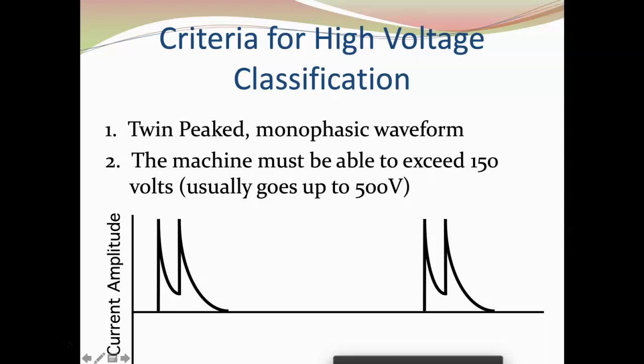We also know that the high voltage device is capable of delivering up to 500 volts. We can look at that and go, oh my goodness, that's a lot of voltage to be delivering to a patient. The great thing about high voltage pulse stimulation — and the keyword is pulsed — is that the electrical stimulation being delivered to that patient is going to be pulsed. In terms of its name, high voltage, it's capable of delivering up to 500 volts, but it will not actually do that, and we'll talk about why.